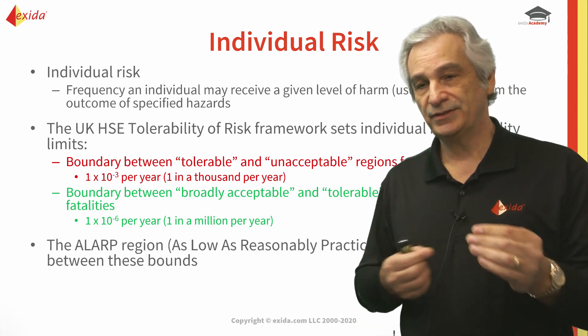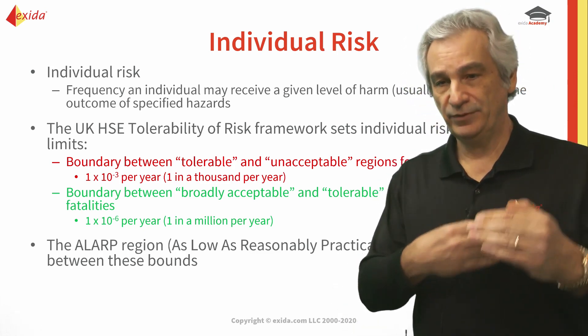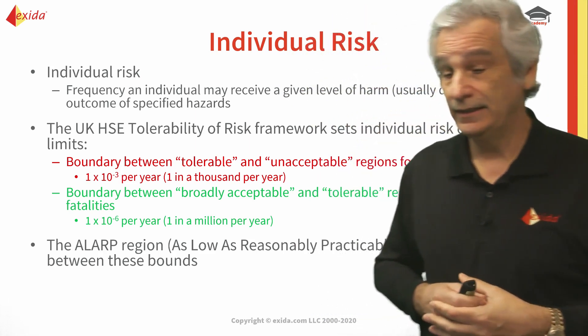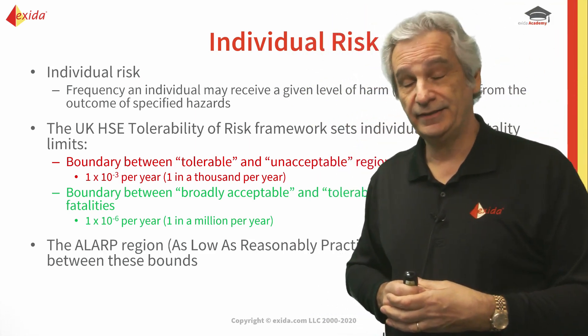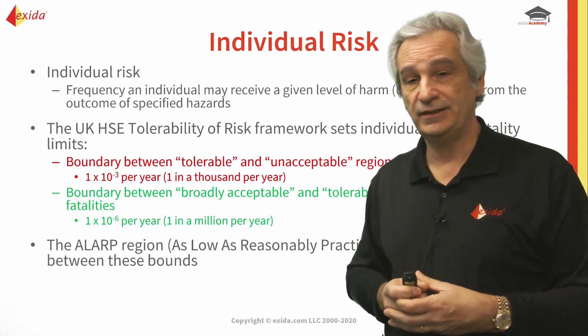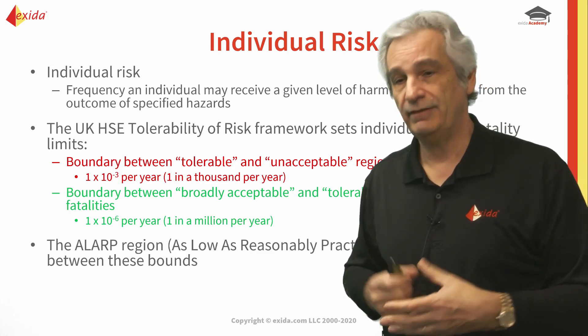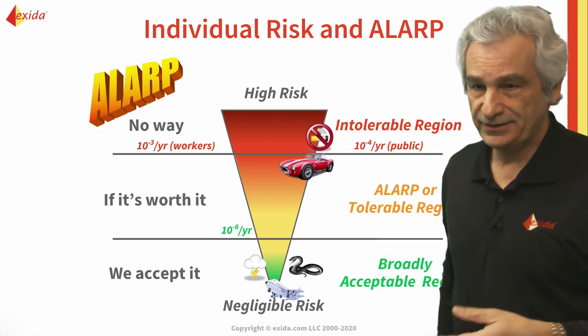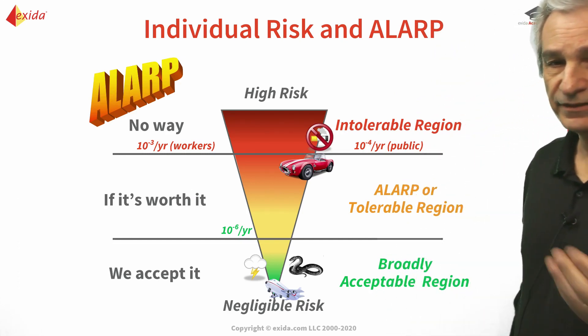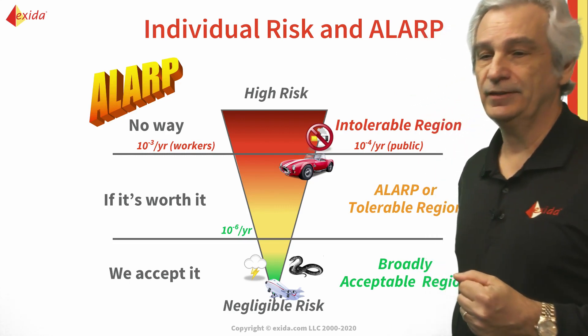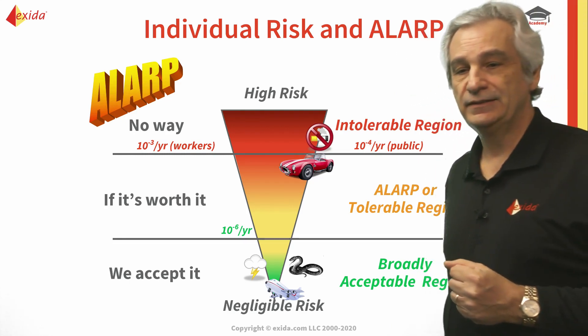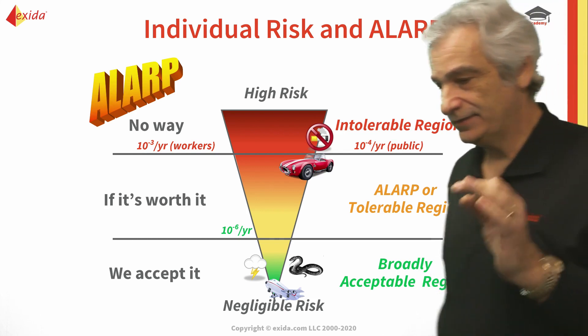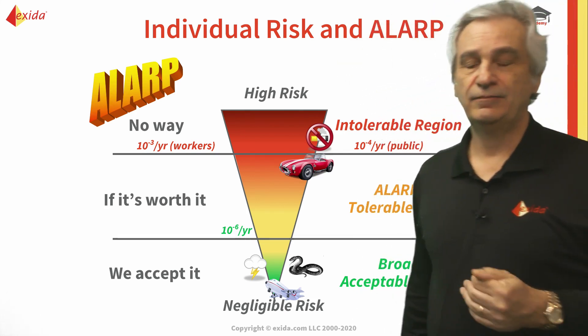Whatever tolerable risk you define must be within the ALARP boundaries. One client had a tolerable risk of 10⁻³ because their installation was unmanned — someone only went in once or twice a year for routine maintenance, so it was not manned 24/7/365. ALARP ranges from 10⁻³ down to 10⁻⁶ for plant workers and 10⁻⁴ to 10⁻⁶ for the public. Most companies define their tolerable risk based on ALARP requirements.